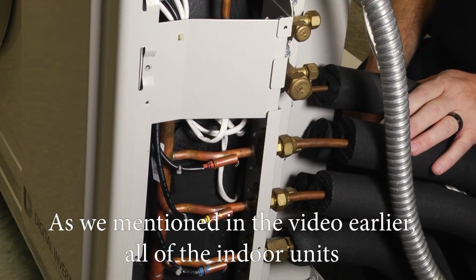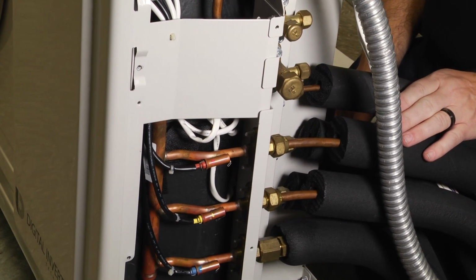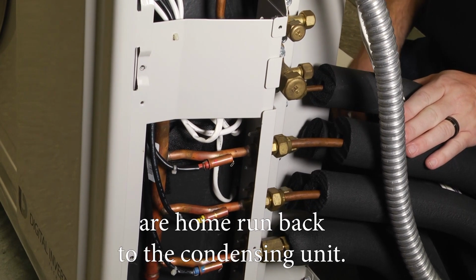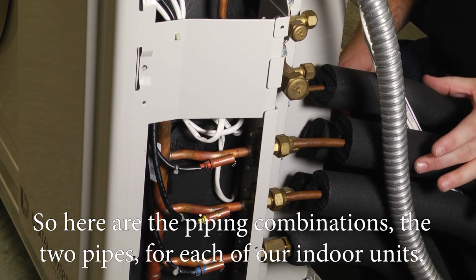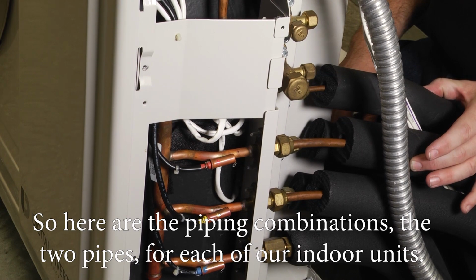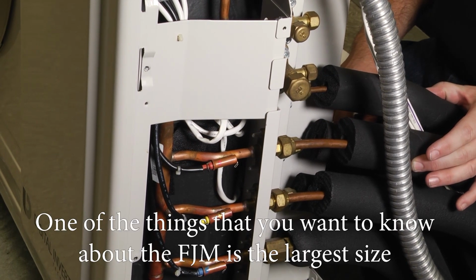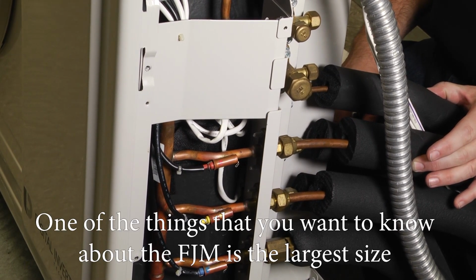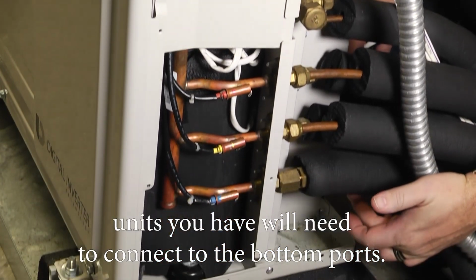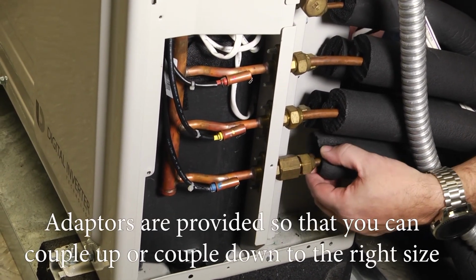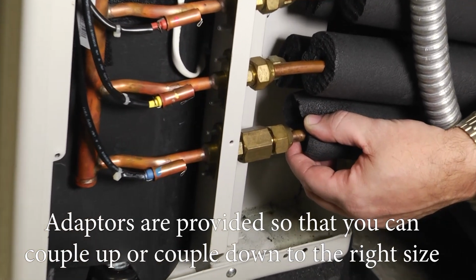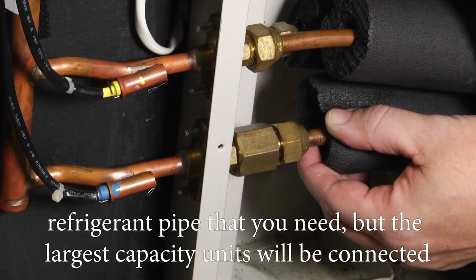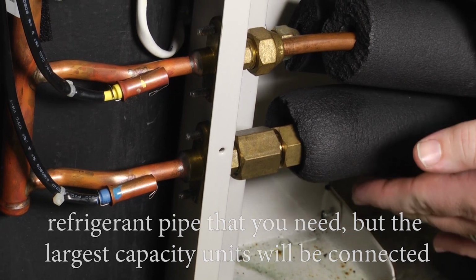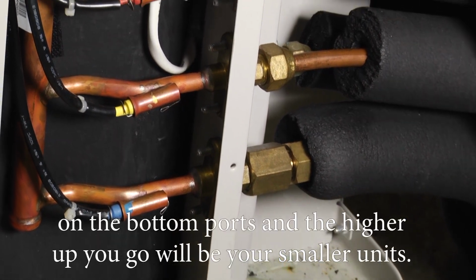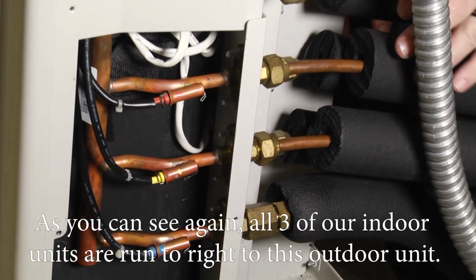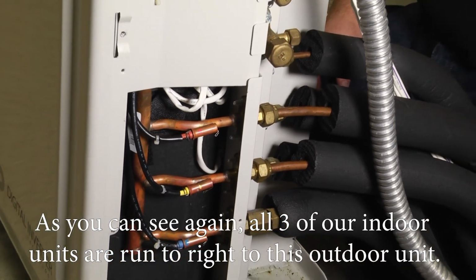So as we mentioned in the video earlier, all of the indoor units are home run back to the condensing unit. So here are the piping combinations, the 2 pipes for each of our 3 indoor units. One of the things you want to know about the FJM is the largest size units you have will need to connect to the bottom ports. Adapters are provided so that you can couple up or couple down to the right size refrigerant pipe that you need. But the largest capacity units will be connected on the bottom ports, and the higher up you go will be your smaller units. And as you can see again, all 3 of our indoor units are run right to this outdoor unit.